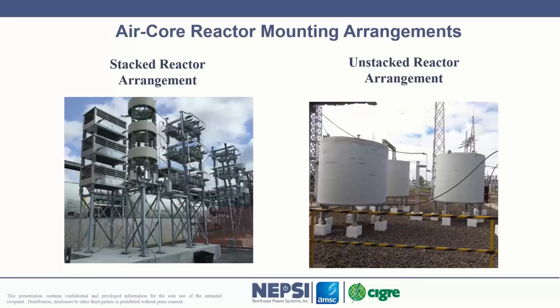Just some different designs here: air core reactors, stacked arrangement. We show it here. Again, this is R, and this is the X of L and the C. So we have a three-phase stacked reactor arrangement, air core. And then here we have the same type of reactors, but at ground level. And they're large, probably a low tuning point here is what's going on.